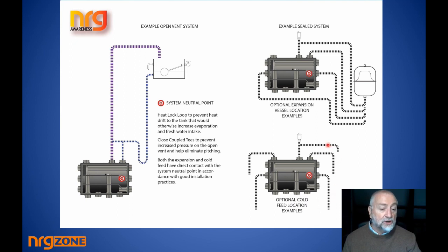Where you bring your cold feed into a system for a pressurized system, I know it's only used for filling, but the benefit is if you do bring it into these points, the water can tumble down over the gap here, fill the system, the air is leaving, being pushed off out, and again you find it just fills the system extremely quickly. And it can vent the system very quickly.